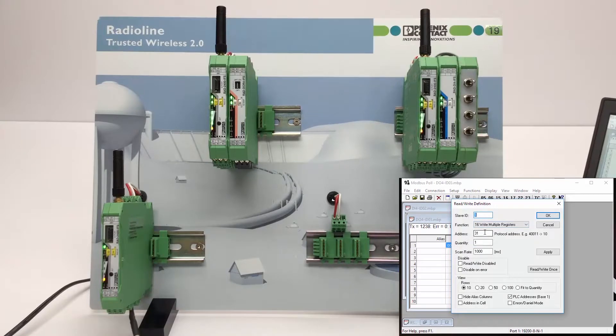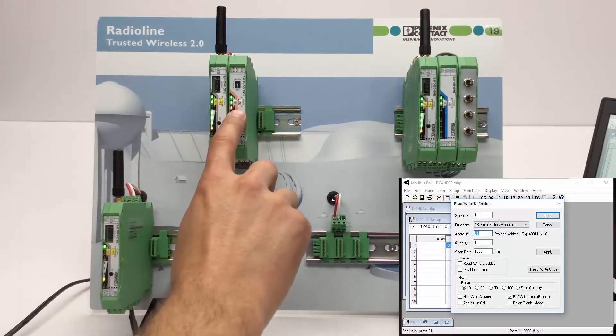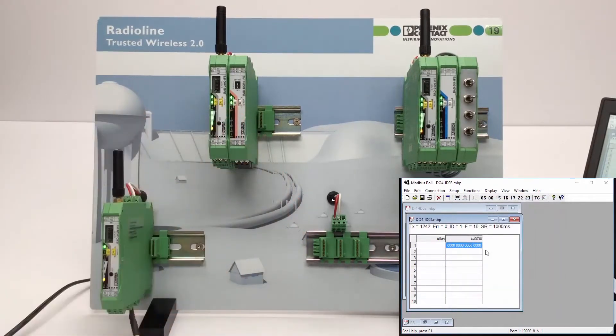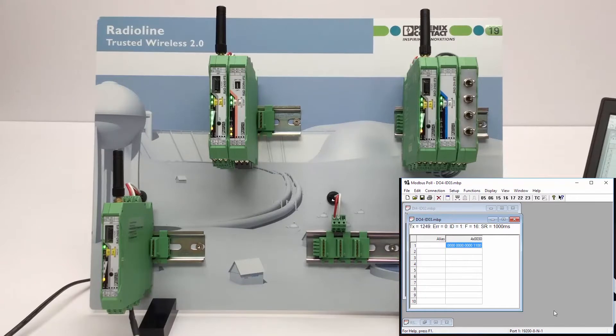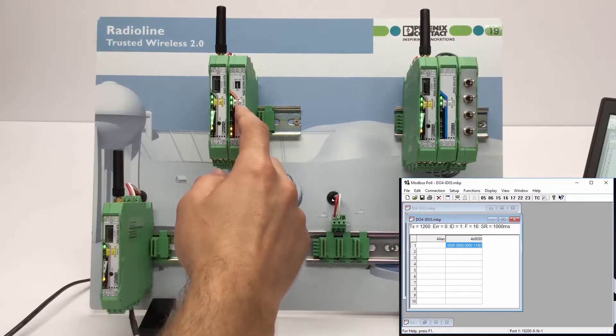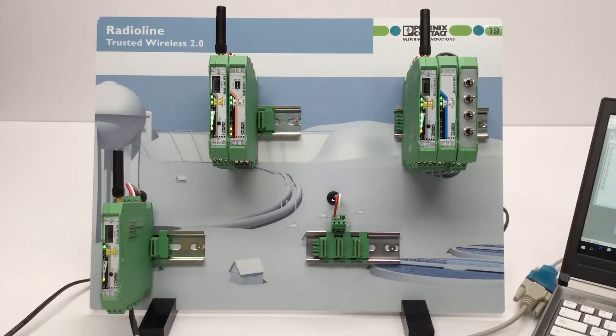The red error LED on the digital output module will flash until the output register is written for the first time. Using function code 16, register address 31 is now addressed by Modbus Poll to activate digital output DO1. The enabled output is seen by the status LED on the I/O module. Now you can see the red error LED on the output module has stopped flashing. The current status of the output can be read back via function code 03.